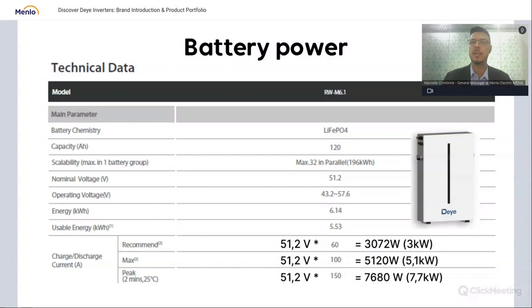Now, looking at the batteries, let me explain in detail what they can do. The manufacturer's recommended charge and discharge current is 60 amps, and at a nominal voltage of 51.2, the battery delivers 3 kilowatt. At the maximum discharge of 100 amps, the battery can deliver 5.1 kilowatt. Then there is a peak of 150 amps, which is 2 minutes at 25 degrees. Please be aware that we have to check the temperatures in your local areas. If it goes above 25 degrees, that 2 minutes will automatically reduce. That peak would be 7.7 kilowatt, and you need to make sure you have the correct inverter connected, because the smaller inverters won't be able to support that.